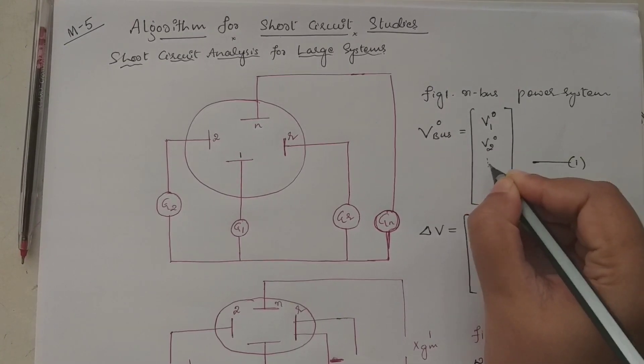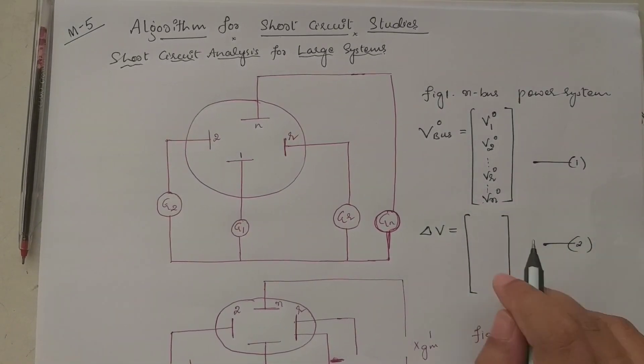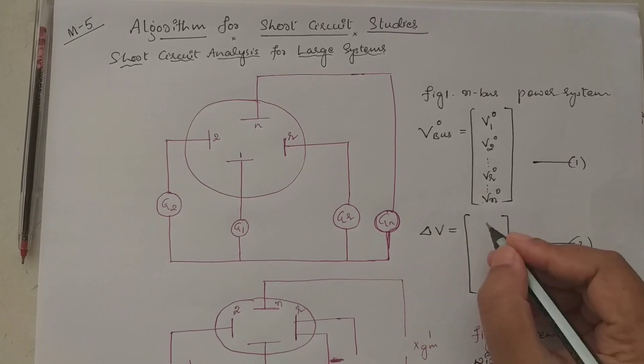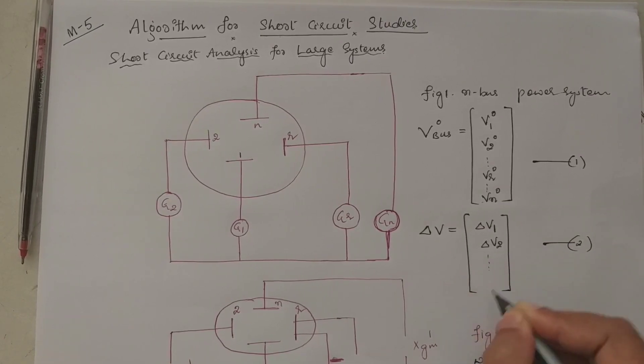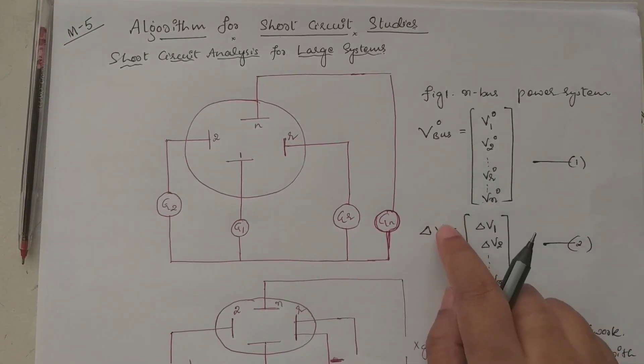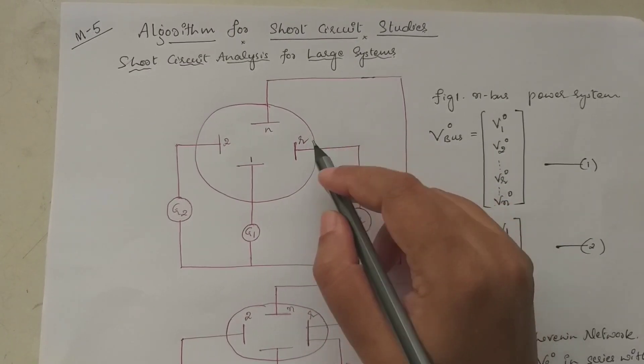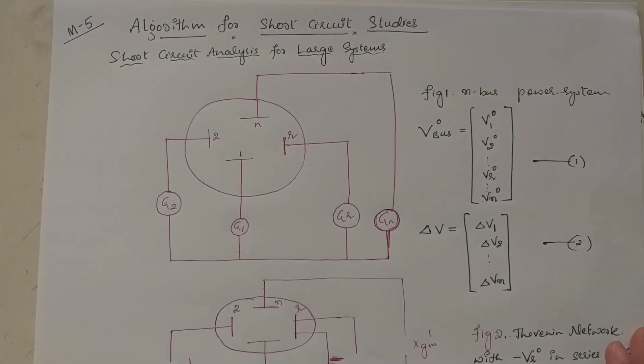The pre-fault voltage V_bus is equal to [V1⁰, V2⁰, ... Vr⁰, ... Vn⁰] — take it as Equation 1. After the fault, the post-fault voltage vector is [ΔV1, ΔV2, ... ΔVn] — take it as Equation 2. Now consider that a short circuit fault occurs at the r-th bus. Figure 2 shows the Thevenin network with generators replaced by transient or sub-transient reactances.